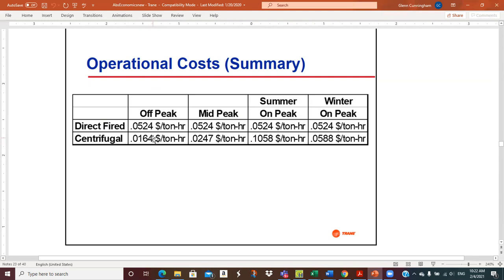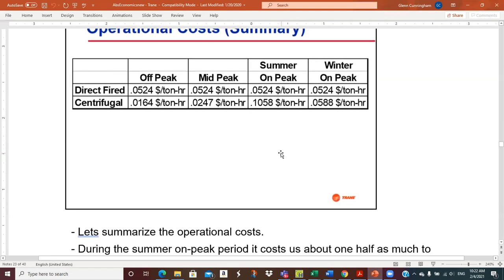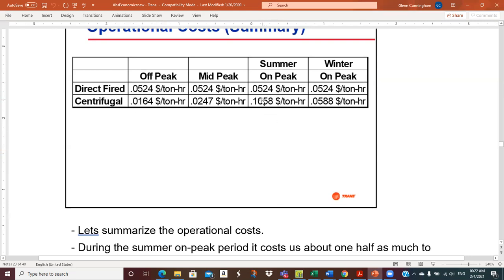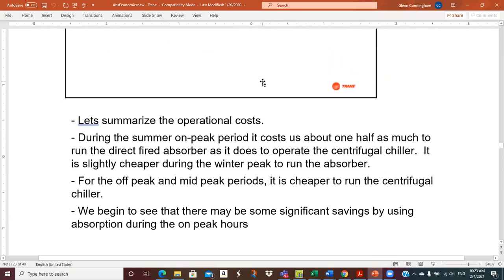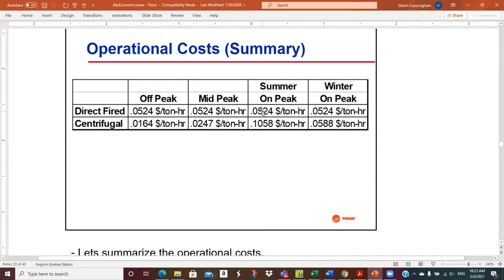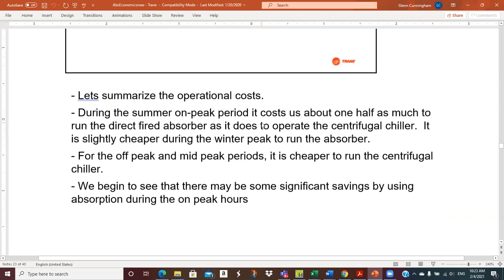Wow, that's really cheap. That's much cheaper than the direct fire absorber. Mid-peak 2.47, but on-peak there's the 10.58, and then the winter on-peak is 5.88 cents per ton hour. So now we get to see where we can generate some savings, because we have a big cost advantage for the absorber compared to the centrifugal for the on-peak summer hours. It's pretty close to twice as much to run. In fact, it's a little more than twice as much, isn't it? Yeah, it'd be 10.48 versus 10.58.